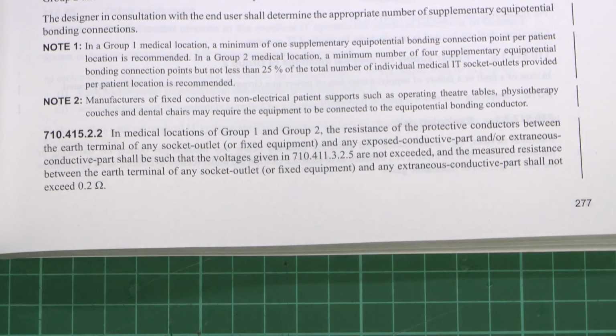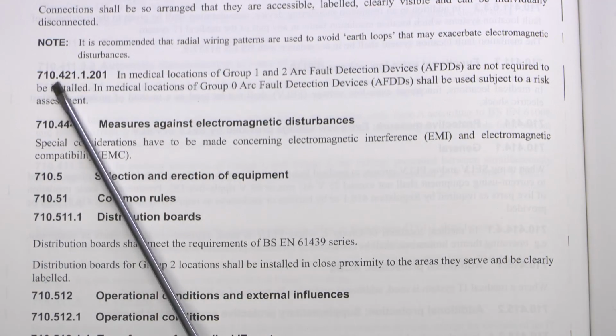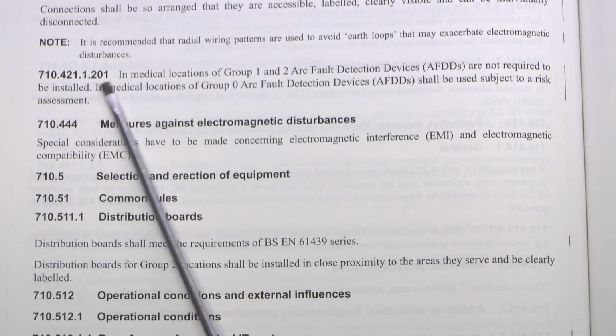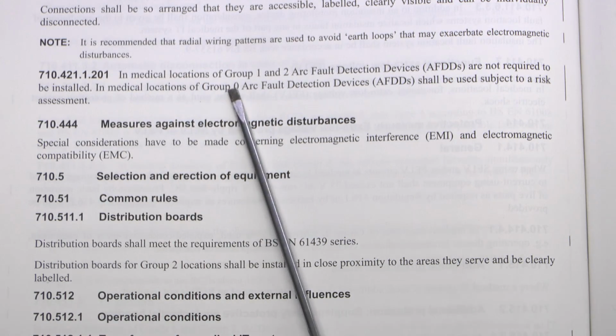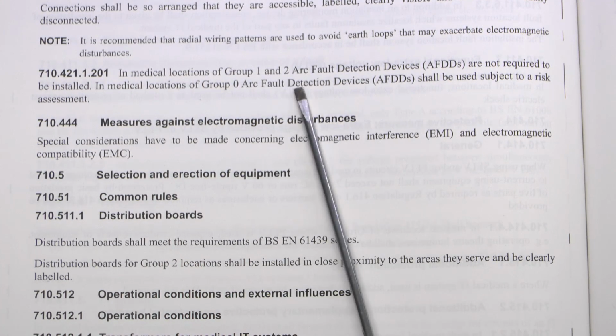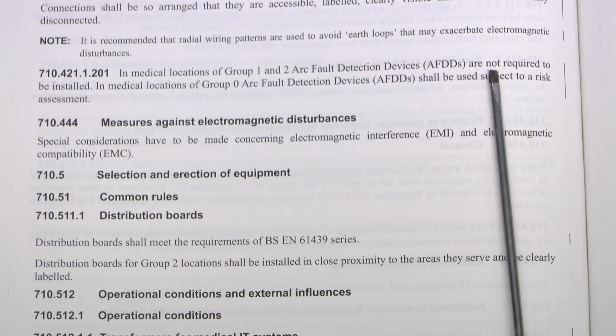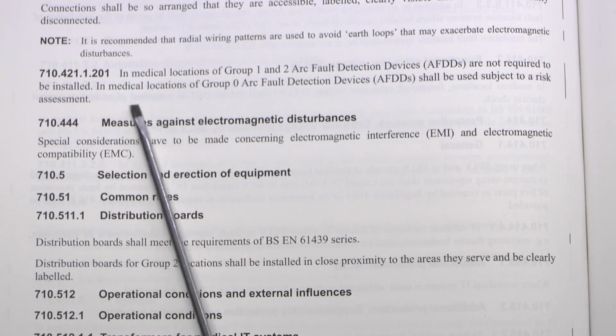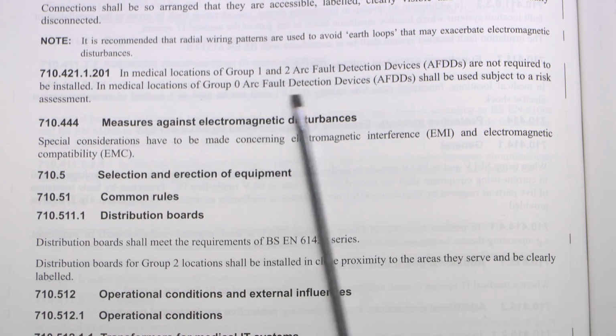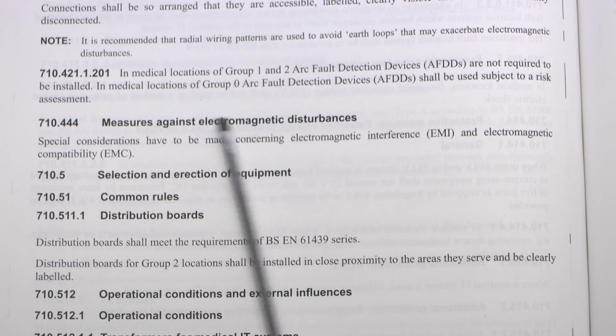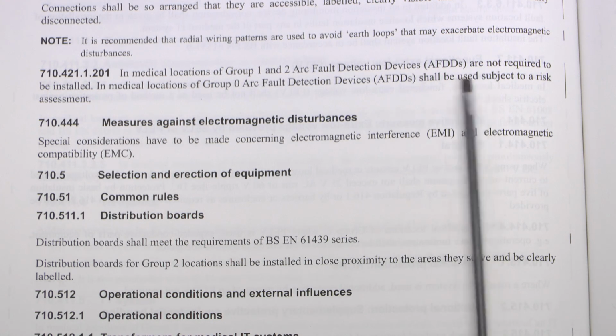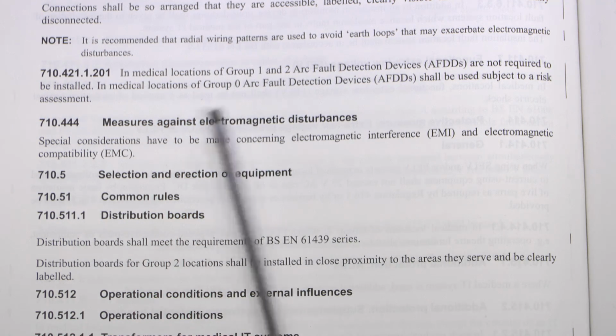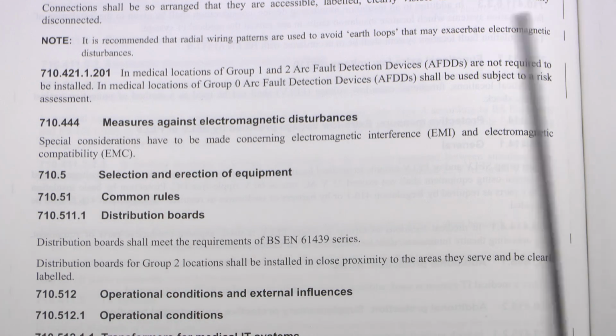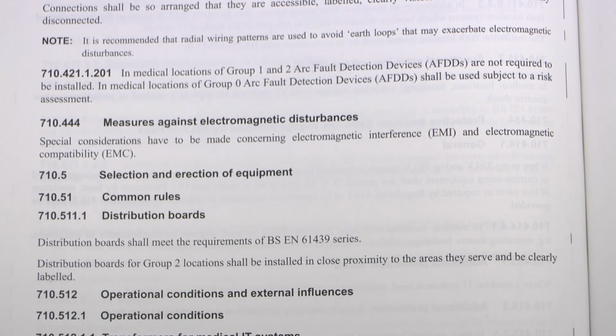Another new one on the page here, we've got 710.421.1.201. In medical locations of Group 1 and 2, arc fault detection devices, AFDDs, are not required to be installed. In medical locations of Group 0, arc fault detection devices shall be used subject to a risk assessment. So they're not required, and you can use them in the Group 0 if desired, and obviously based on the individual circumstances.